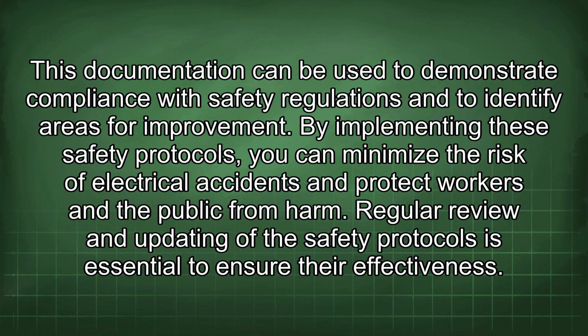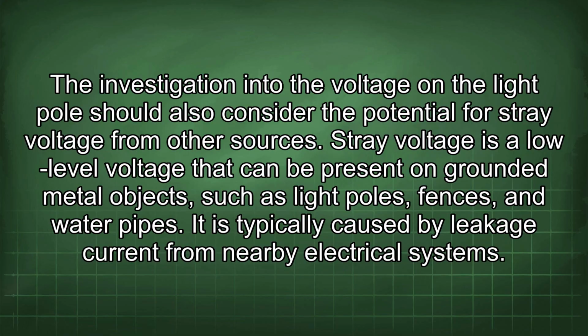By implementing these safety protocols, you can minimize the risk of electrical accidents and protect workers and the public from harm. Regular review and updating of the safety protocols is essential to ensure their effectiveness. The investigation into the voltage on the light pole should also consider the potential for stray voltage from other sources. Stray voltage is a low-level voltage that can be present on grounded metal objects such as light poles, fences, and water pipes. It is typically caused by leakage current from nearby electrical systems.